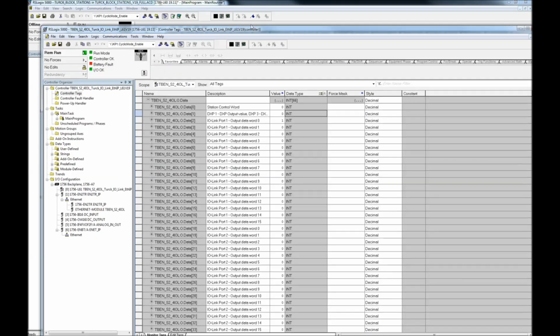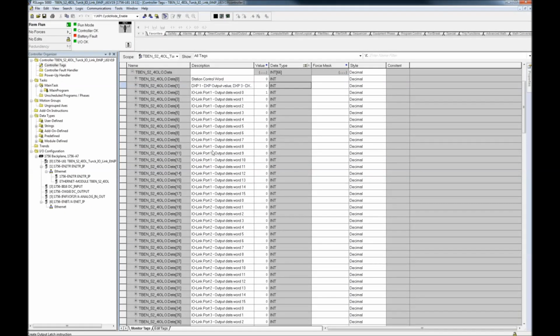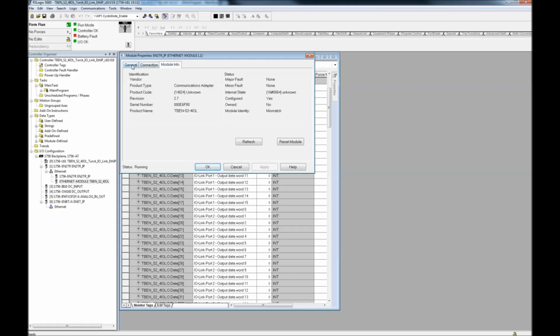The ACD file, so basically it came through here with all these modules. Then I simply found the TBEN-S2-4IOL. I then dragged that to my project. It had a host name of A160. I changed that to the IP address there.